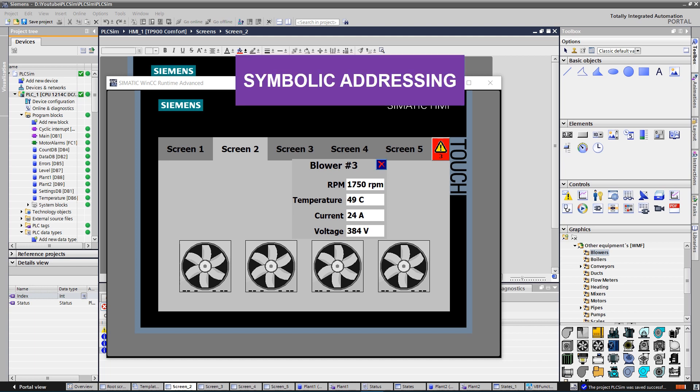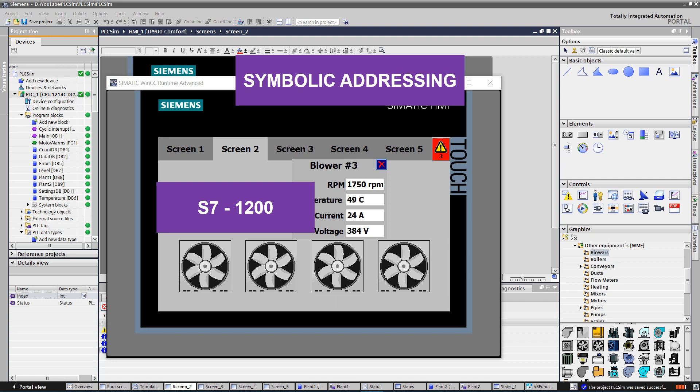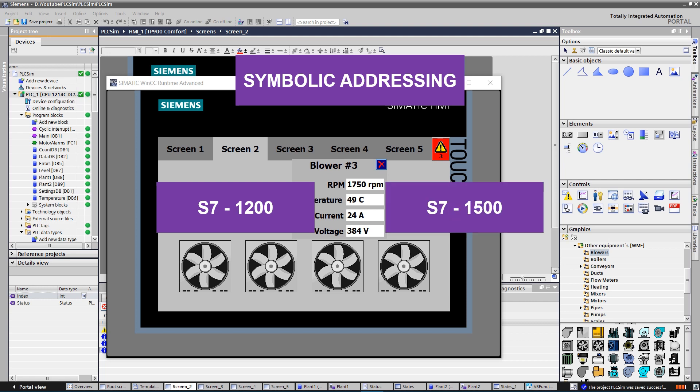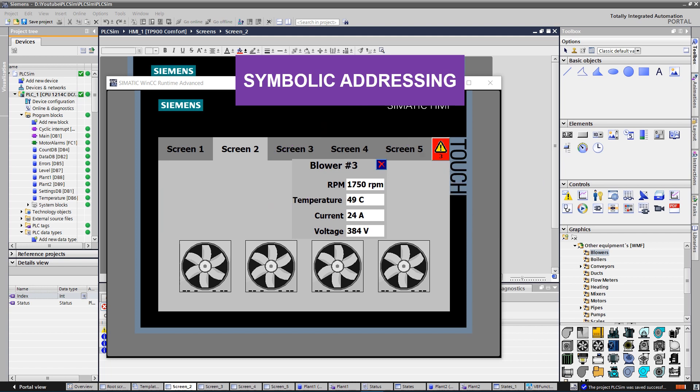Multiplexing with symbolic addressing is supported by S7-1200 and S7-1500 communication drivers. By multiplexing with symbolic addressing, you access array elements of an array tag in a data block by means of a multiplexing tag and an index tag.